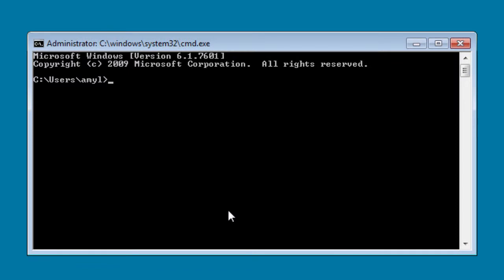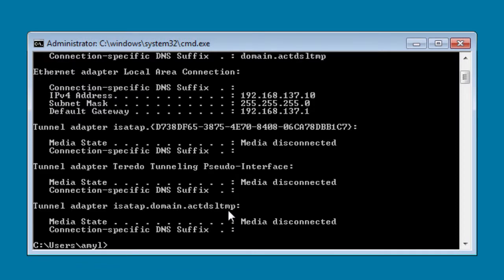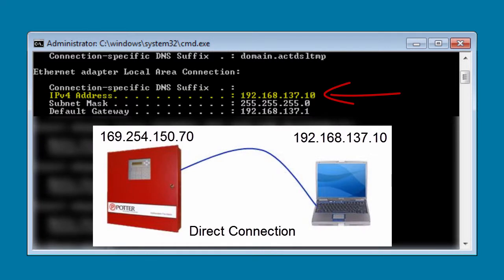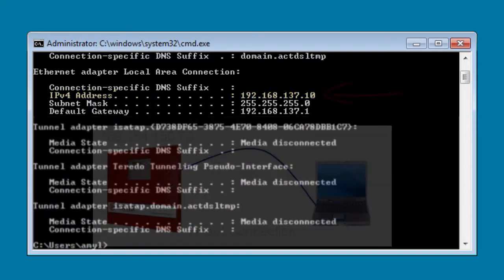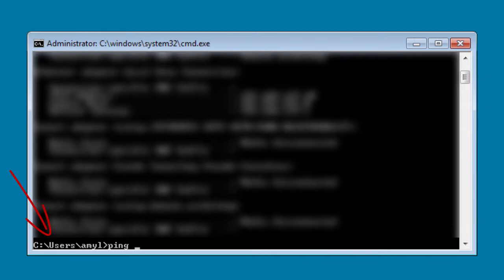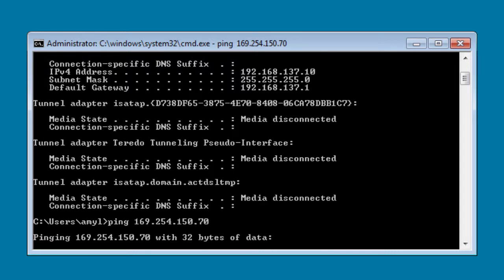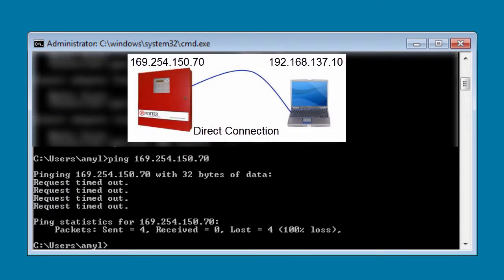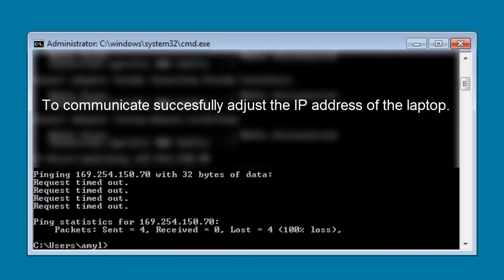In the event that you do not have similar IP addresses — for example, if the IP address of my laptop computer is 192.168.137.10 and I am directly connected to the fire alarm control panel whose IP address is 169.254.150.70 — when I ping the panel from the command prompt by typing in that IP address, it will time out, which means I am not successfully communicating with the fire alarm control panel. What is happening is that my computer has a static IP of 192.168.137.10, and that does not work with the IP address the fire alarm control panel has.